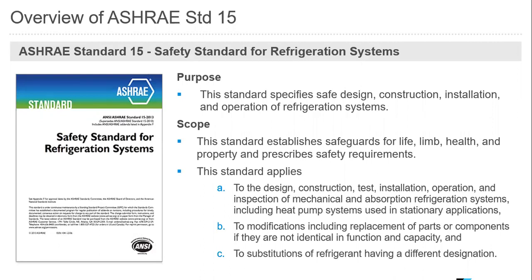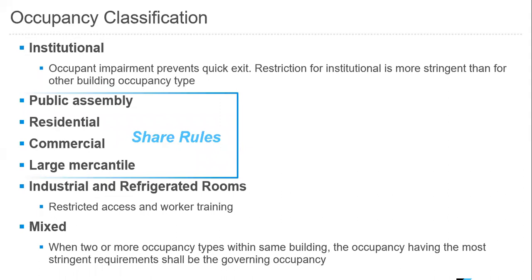ASHRAE standard 15. So ASHRAE 15, this is something I know we covered at length several months back last year. The purpose of ASHRAE 15 is to specify safe design, construction, and installation of VRF systems, but specifically operation of refrigerant systems. This establishes safety for occupants in buildings, and applies to the design, construction, modifications, and then substitutions for systems that have a different designation. So there are different occupancy classifications.